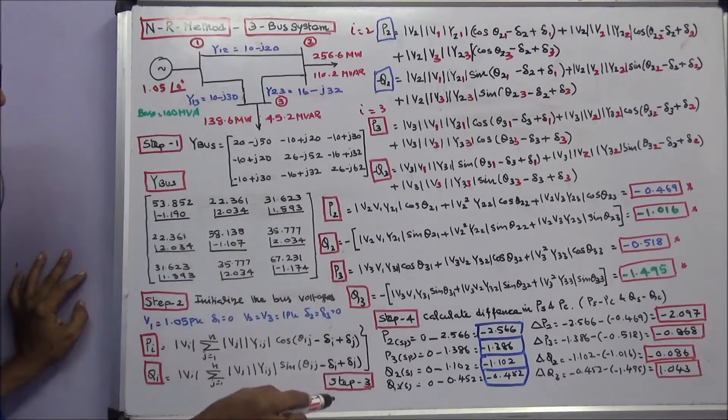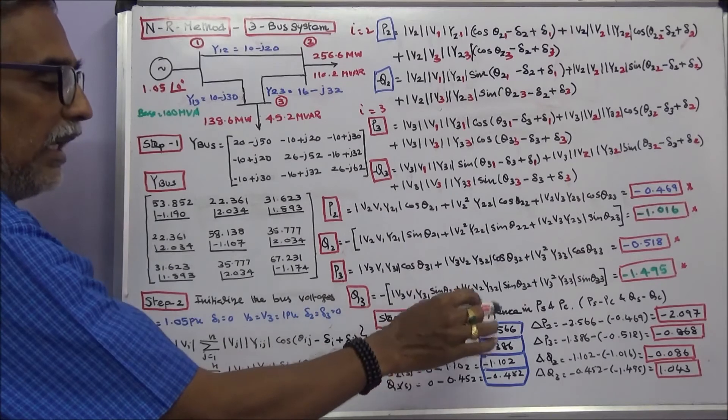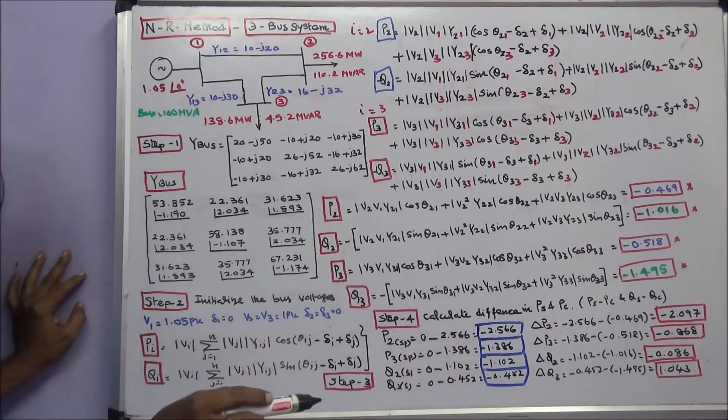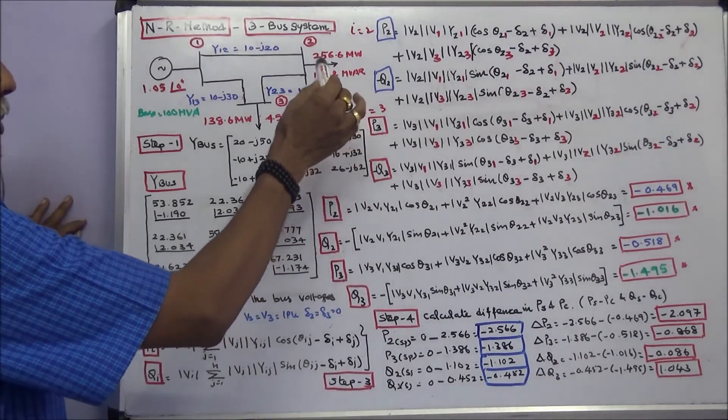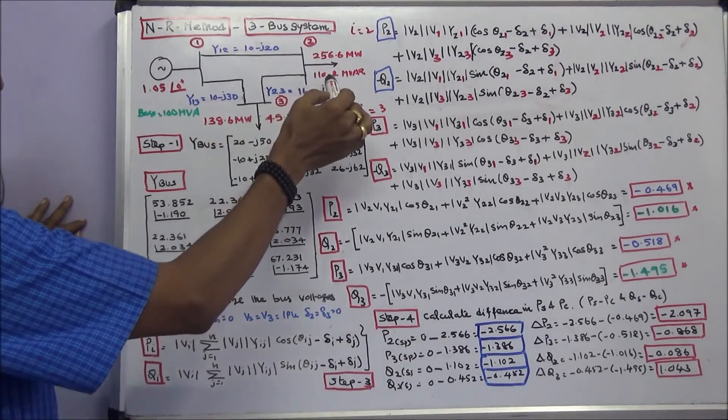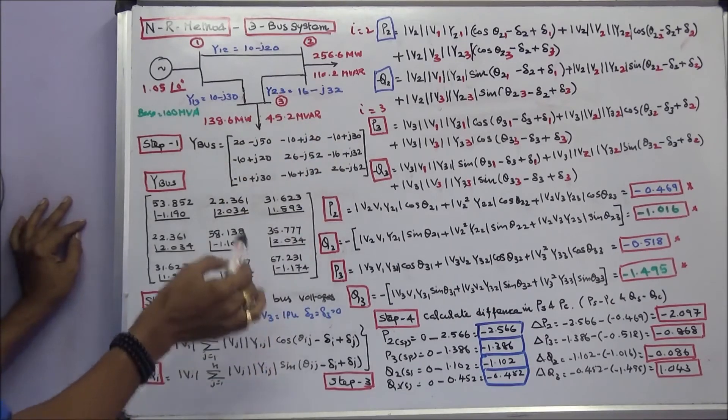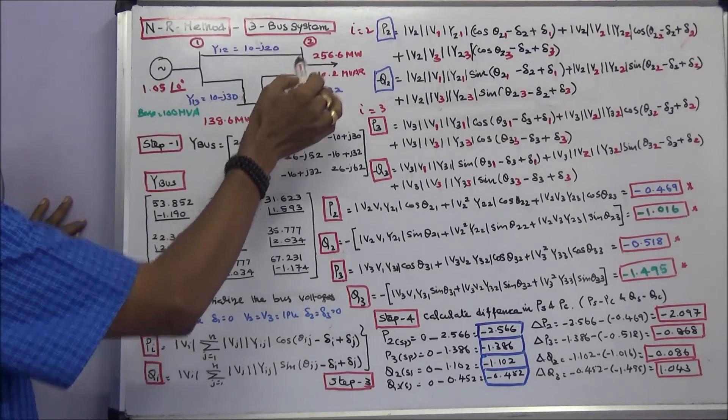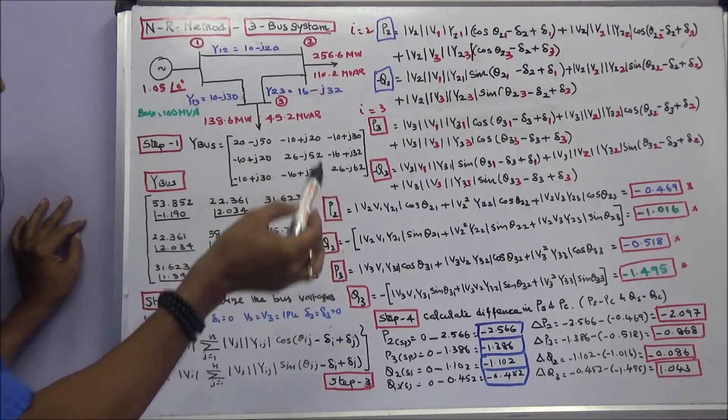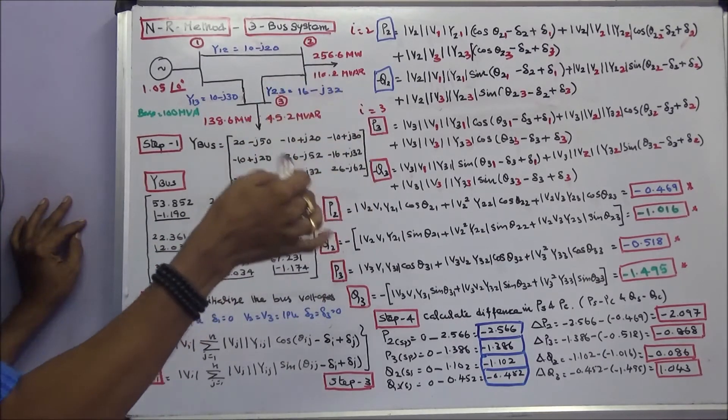The fourth step is we have to find the difference, that is del P2, del P3, del Q2, del Q3. First we have to calculate P2 specified, P3 specified, Q2 specified and Q3 specified. Base MVA is equal to 100. The bus 2 and bus 3 are load buses, therefore the real and reactive power generation is 0.